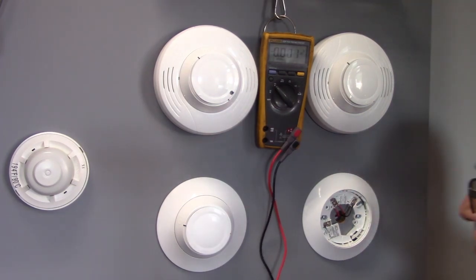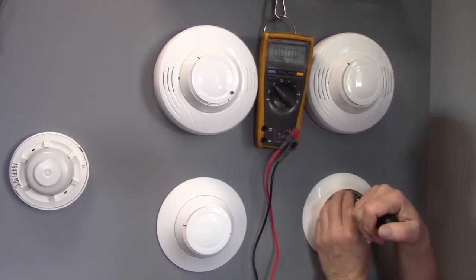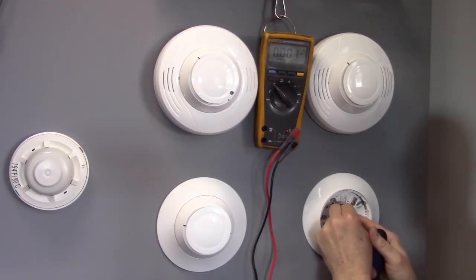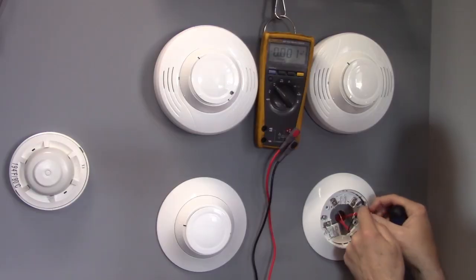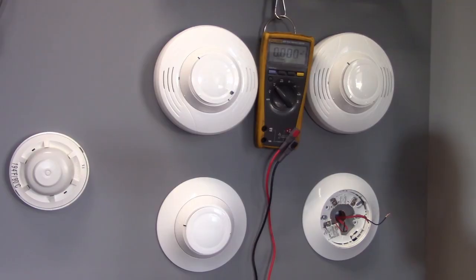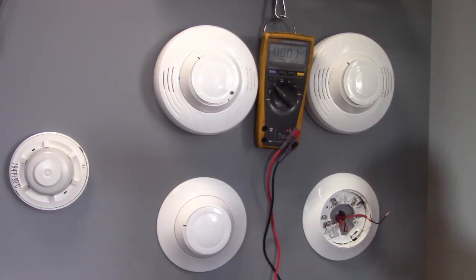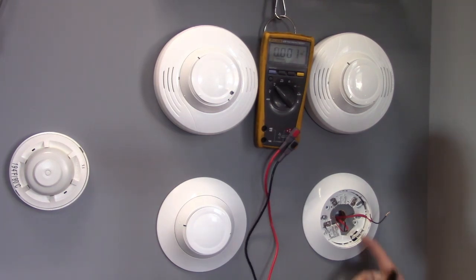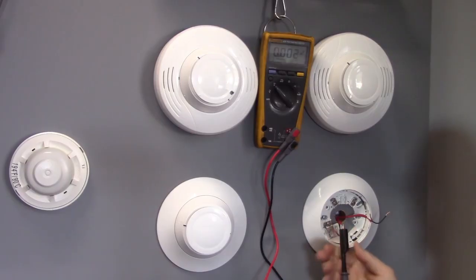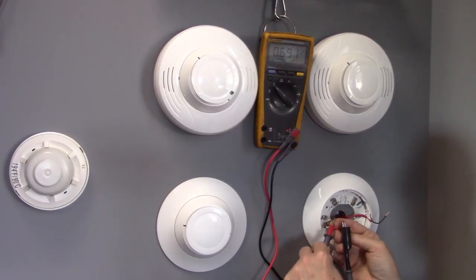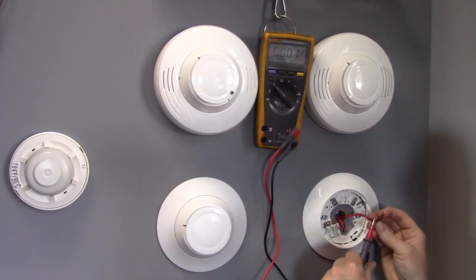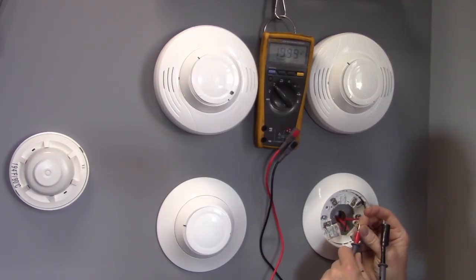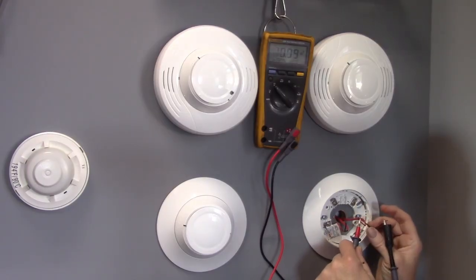So what we're going to do now, separate these wires. We've got two cables coming in. One of these cables has voltage on it that's going back to the fire panel. The other cable most likely will not have voltage on it because it's going away from the fire panel. So the first thing to do is identify which one of these cables goes towards the fire panel. So we're going to have to measure voltage. So there's no voltage on this one. This one goes away from the fire panel.